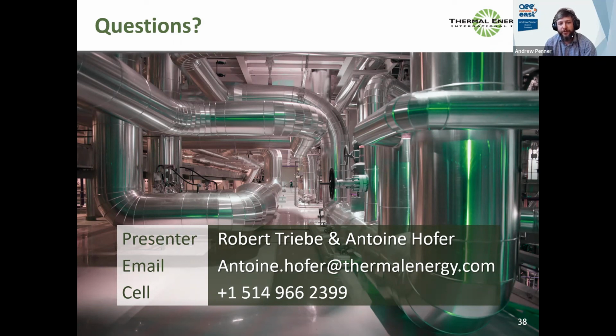What's the maintenance frequency for the heat recovery economizers that you've been talking about through this presentation? On natural gas, nothing. Natural gas is nice and clean, really virtually nothing. And we do have systems running for 30 years, so a 30-year lifetime's not speculative. I've seen direct contact systems from multiple suppliers installed and working for over 30 years with very little cleaning. If you're running a dirty fuel, you're going to be looking at cycles of 6 to 12 months.